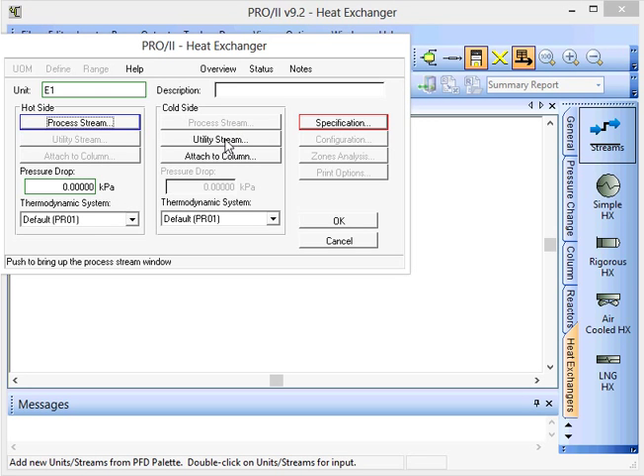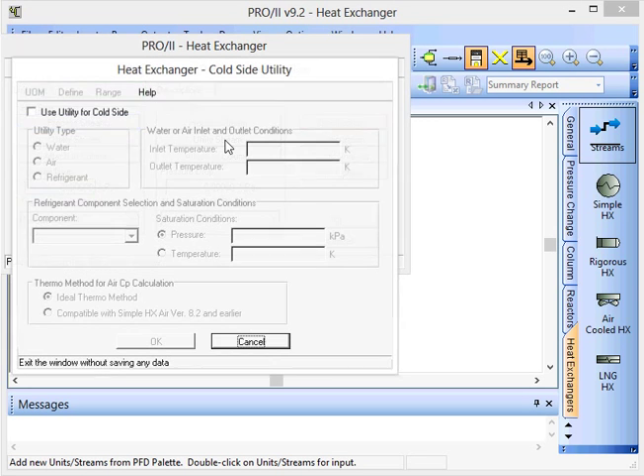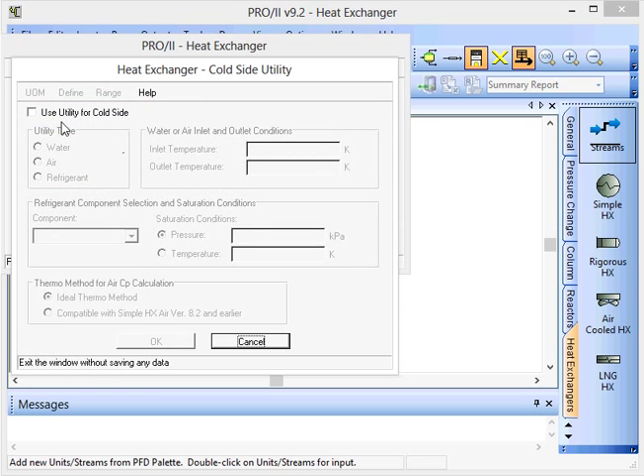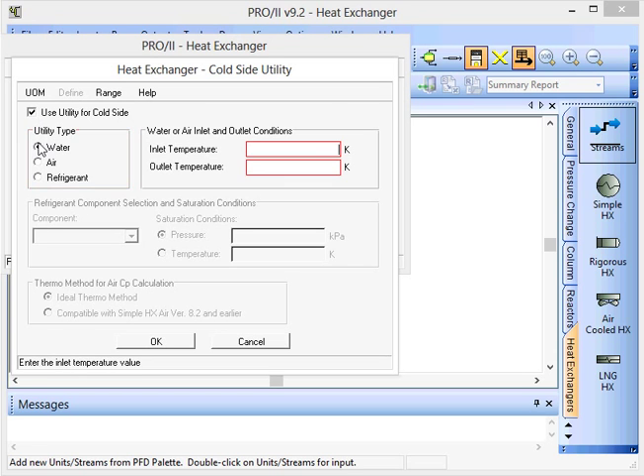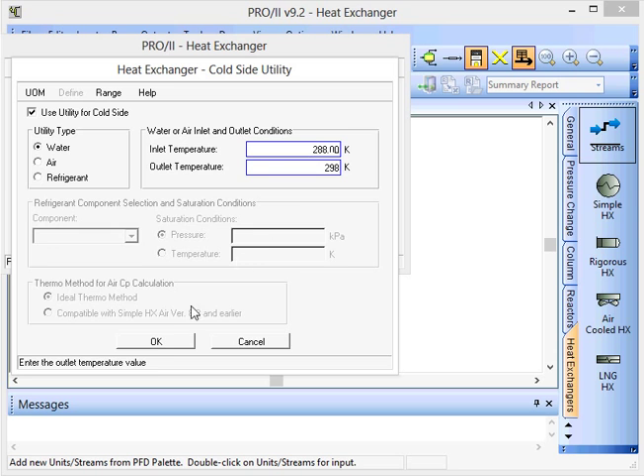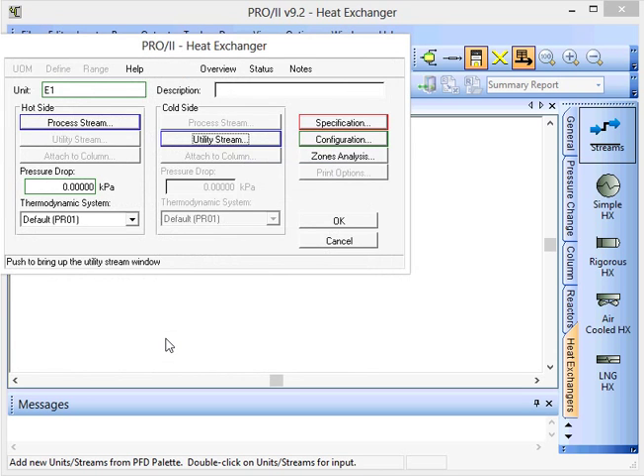On the cold side we will use a utility stream, so we have to check this box here. For this example we use water, with an inlet temperature of 288 Kelvin and an outlet temperature of 298 Kelvin. So we'll allow a 10 degree temperature rise on our cooling water.